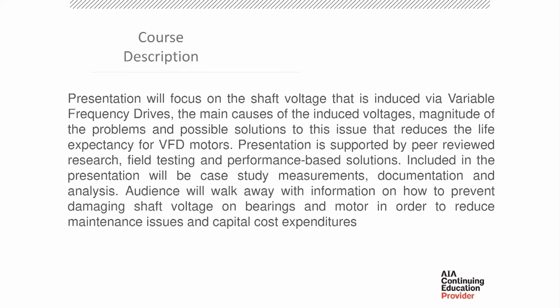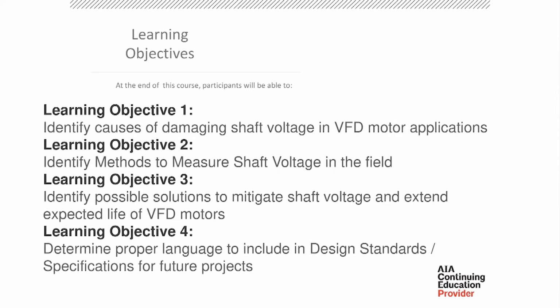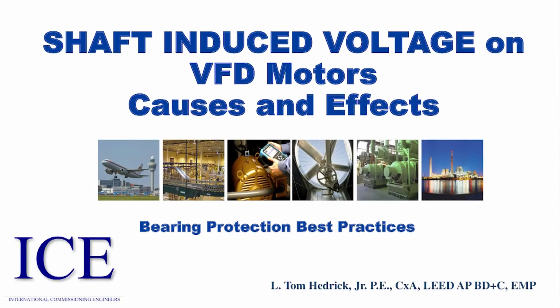In the presentation, you will see case study measurements, documentation, and analysis. Audience will walk away with information on how to prevent damaging shaft voltage on bearings in the motor in order to reduce maintenance issues and capital cost expenditures. Our objectives for today: number one, identify causes of damaging shaft voltage in VFD motor applications. Number two, identify methods to measure the shaft voltage in the field. Number three, identify possible solutions to mitigate shaft voltage and extend life expectancies of VFD motors. And number four, determine proper language that can be included in standard specifications for future projects. So let's get started.